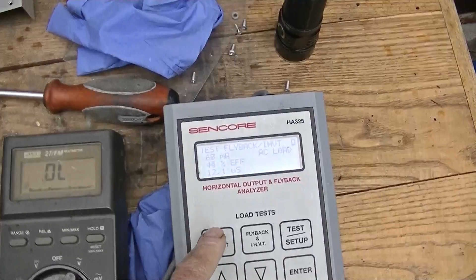That indicates that what that's doing is it's at a low level powering up the high voltage part of this transformer, so nothing's shorted, at least not at a low level. So we got a problem on the drive side, not the secondary.